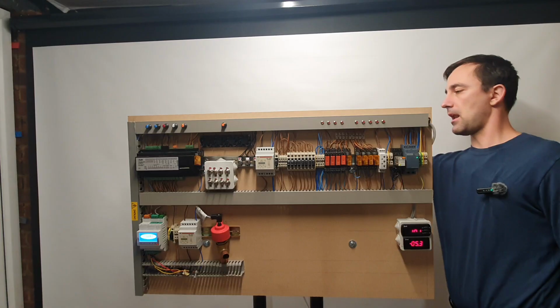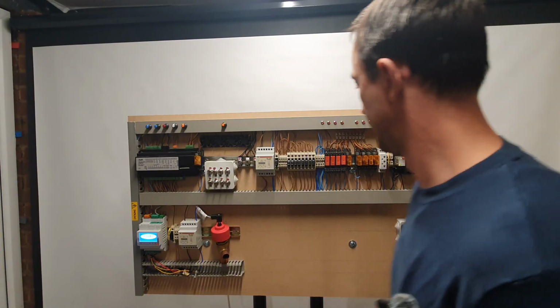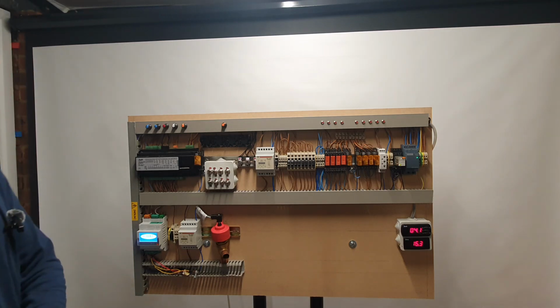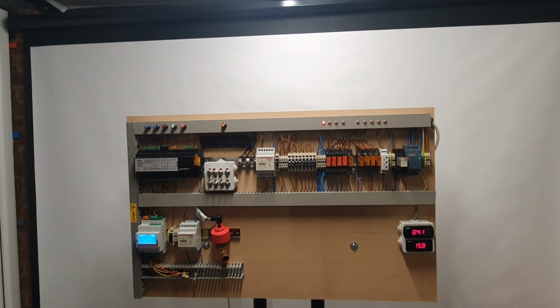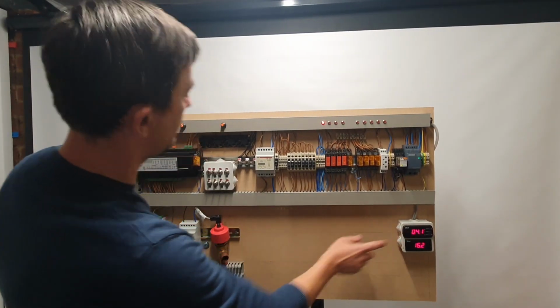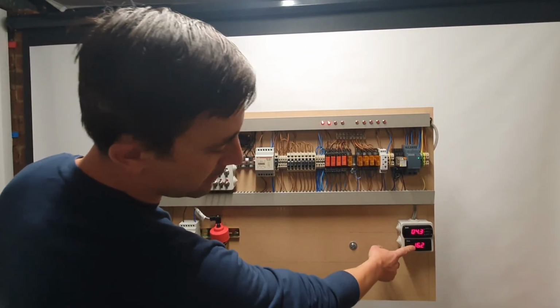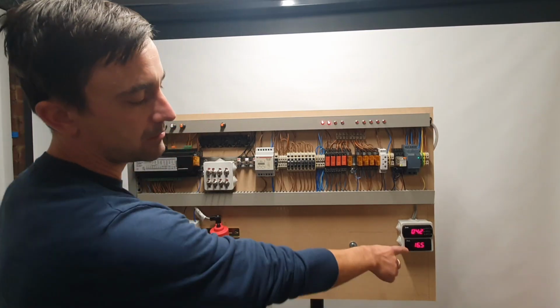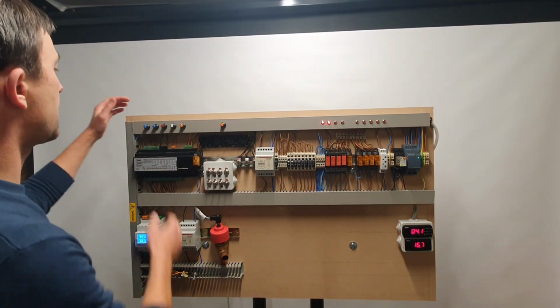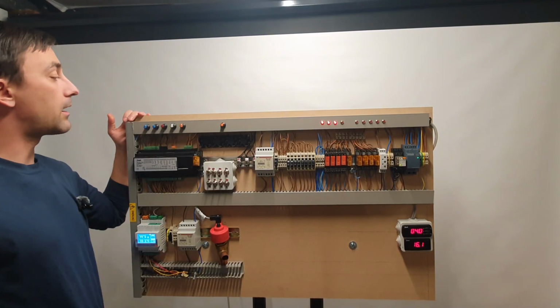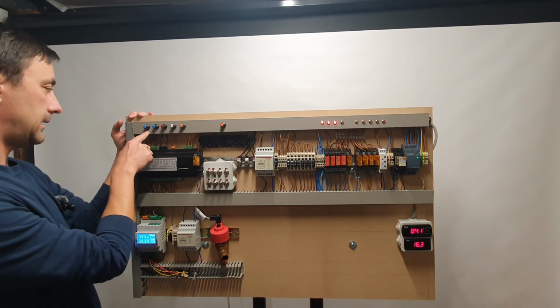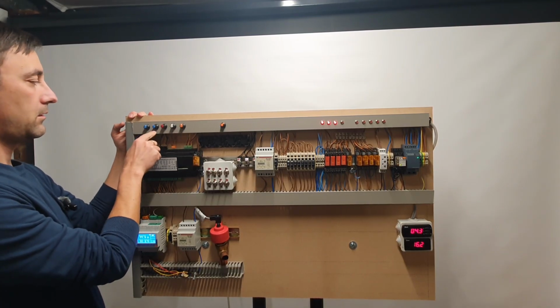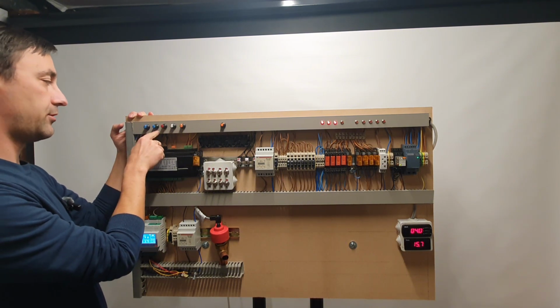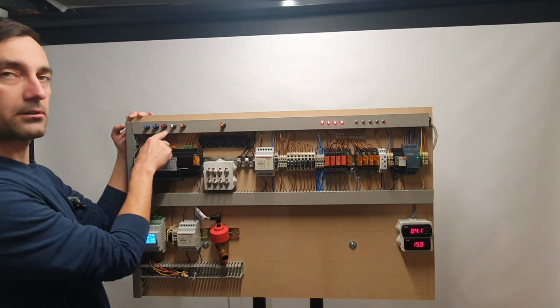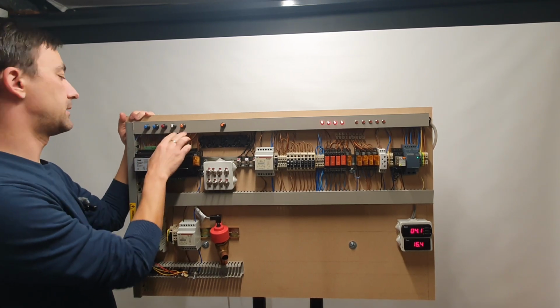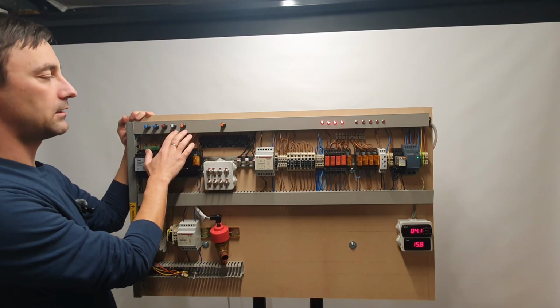Here we are. It's alive. Silly me. Yes, so my pressure is 4.2 bar. I'm just going straight to it. My suction is 4.1, my discharge is 16.5 bar. These are my potentiometers, as you've seen them on my first panel. We have LT, pressure transducer, HT, discharge, and 2 more for probes, but they're not wired. So these are extras in case I need them in the future.